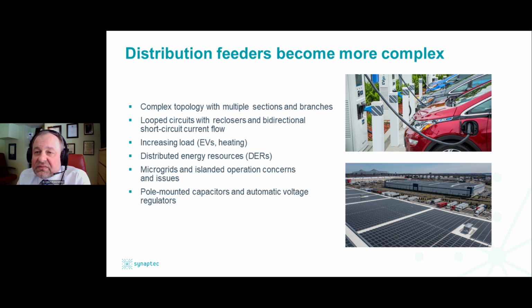And then this micro power system that we keep calling a feeder has all the other features of an energy distribution apparatus. So you will have pole-mounted capacitors in order to maintain voltage profile and provide power factor compensation. You may have automatic voltage regulators. So for all economical reasons, we have this complicated structure that we refer to as just a distribution feeder, and we try to protect it with time overcurrent protection.